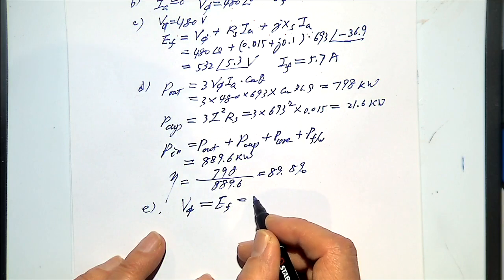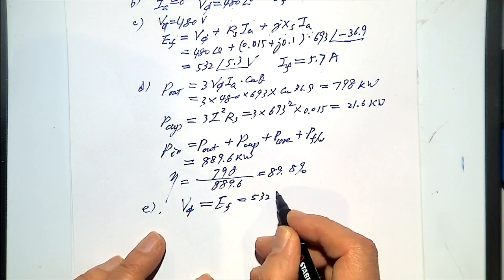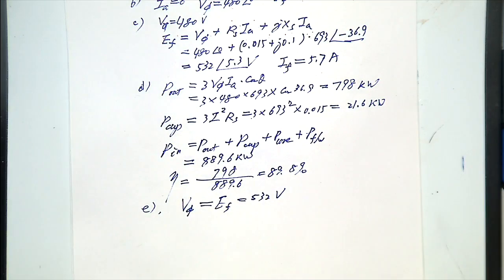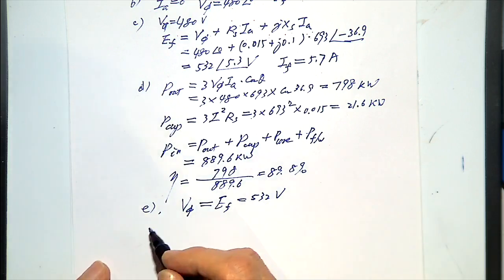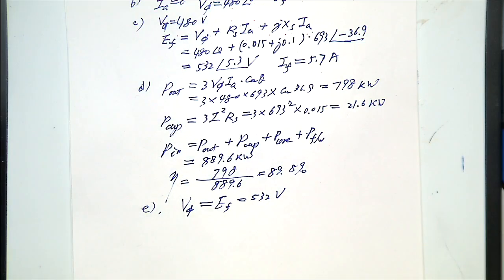That will be 532 volts, because when the load suddenly drops, my magnetic field can't change instantaneously, my driver can't change instantaneously, so my terminal voltage equals my back EMF voltage, which is 532 at angle 5.3 degrees.